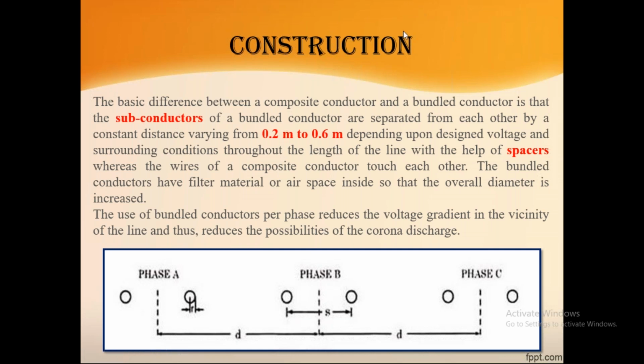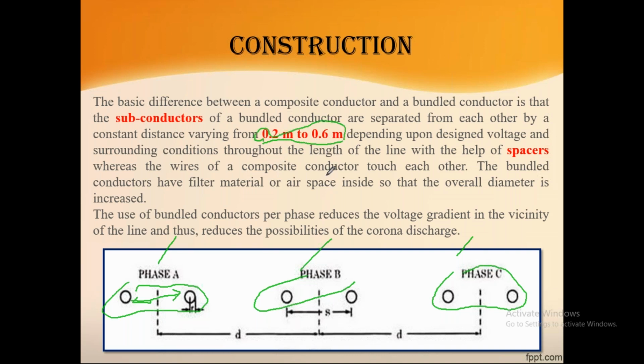Now I am considering a three phase system, let's consider phase A, phase B and phase C. Each phase has two subconductors, called a bundle conductor. So this is one bundle conductor, and this is the second one, and this is the third one. Now our question is, what is the distance we have to keep between these two subconductors? That is the important question. That is 0.2 meter to 0.6 meter. So this is a very important question for your competitive exams. What is the requirement of space between each subconductor in the bundle conductor? That is 0.2 meter to 0.6 meter, and this is maintained by the spacers.